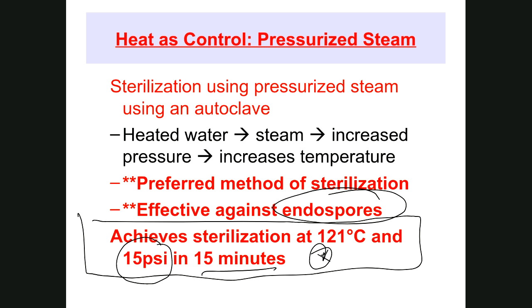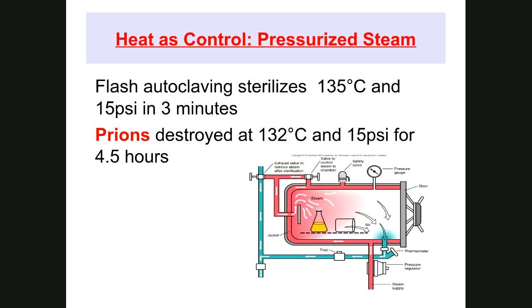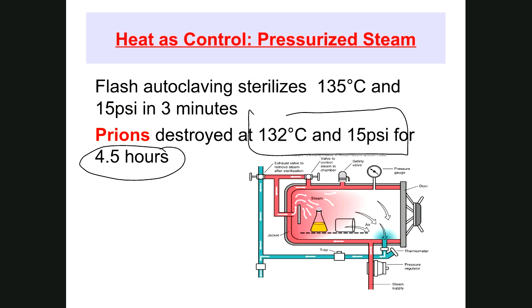Does not kill prions, at least not those parameters. You have to increase everything to kill prions. So 132, 15 psi, 4.5 hours will kill prions. Flash autoclaving for about 3 minutes, increase temperature, same pressure, and that will lower the time of sterilization.